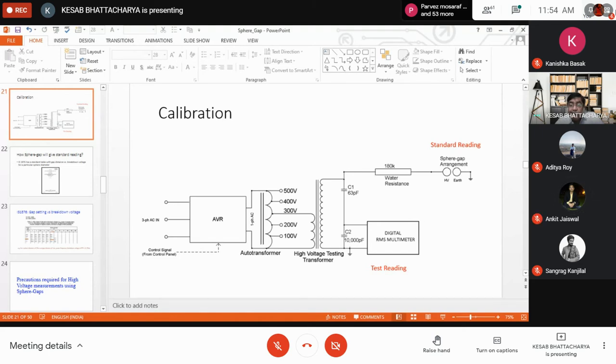Yes, sir. So that is done in order to ensure the existence of a free electron or initiating electron in the gap at the time of application of voltage. But in IS specification 1876, two conditions have been mentioned, particularly where this irradiation is necessary. The first condition is this. When you want to measure any voltage whose magnitude is 50 kV peak or less, then you have to irradiate the gap, whatever may be the diameter of the sphere.